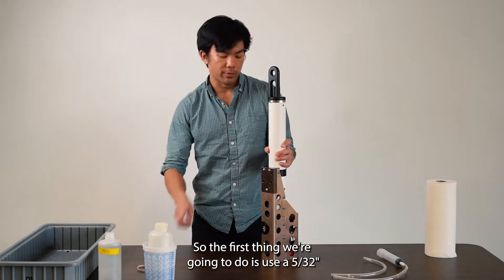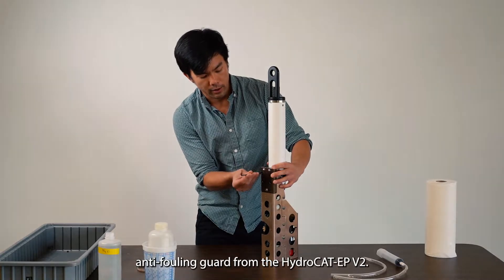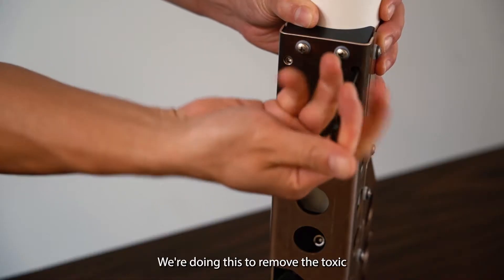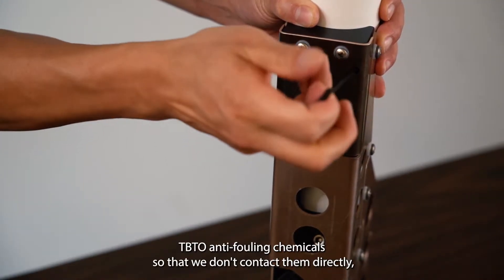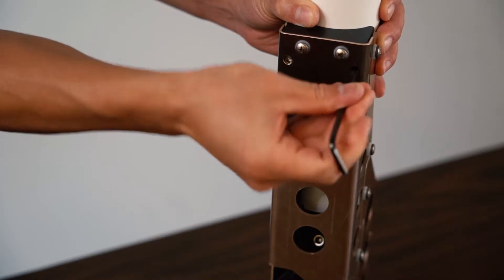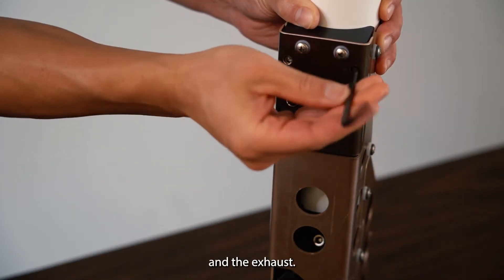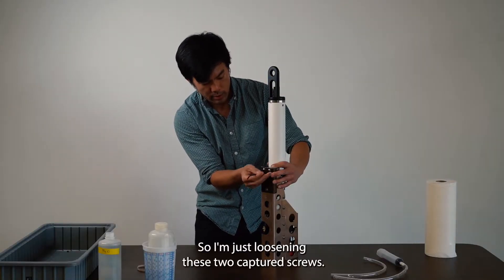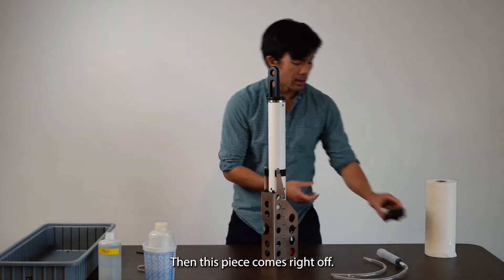The first thing we're going to do is use a 5/32 Allen key and remove the anti-fouling guard from the HydroCat. We're doing this to remove the toxic TBTO anti-fouling chemicals so that we don't contact them during cleaning, and also to expose the hose barbs of the intake and the exhaust. I'm just loosening these two captured screws and then this piece comes right off. Set that aside.